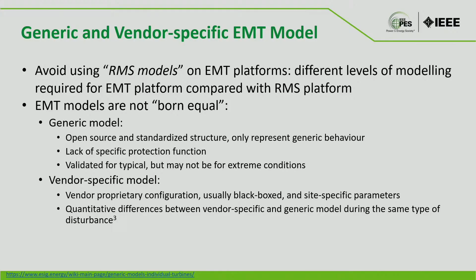So where have EMT models been used? These examples are from Australia, but it's pretty common across other system operators. It can be used in system operation to look at converter-driven interactions and system strength limits. It can support inverter-based resources by developing operating envelopes—for example, determining how much inverter-based resource your system can support given the available synchronous machines, and that you can't support more than that without bringing additional system strength into the grid. It can also be used for assessing complex phenomena such as torsional mode oscillation, commutation failure, and extended commutation failure.